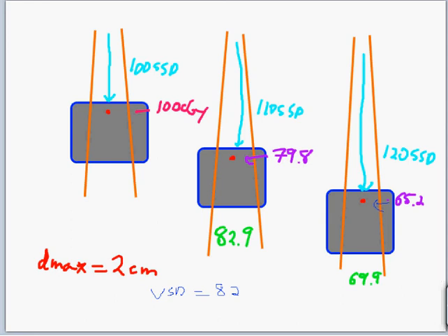And so you might ask, we basically have output factors here. That's what we measured. If you're measuring these things to get the virtual SSD anyway, why don't you just take a couple more measurements and have those in the book? You wouldn't have to do this gap calc. But physicists are busy people, and if we're going to say take a measurement at 105 as well and 115, that could take hundreds of seconds, and we're busy people. So we came up with this complicated math way to do it instead of just a simple measurement.